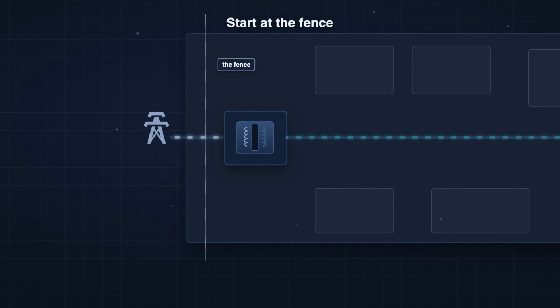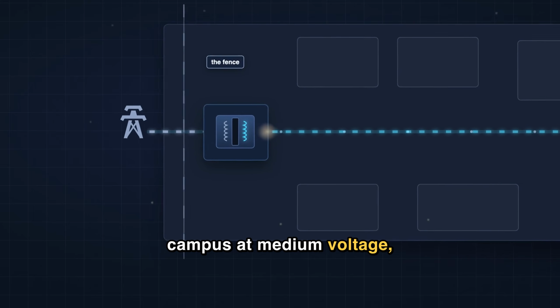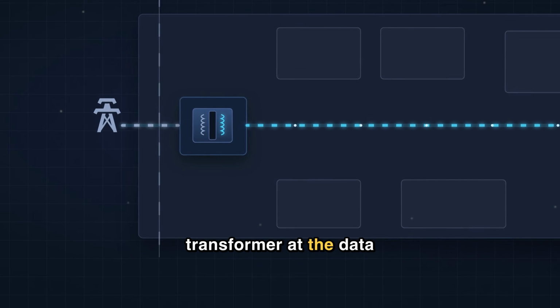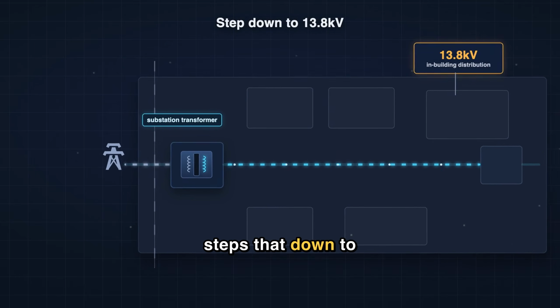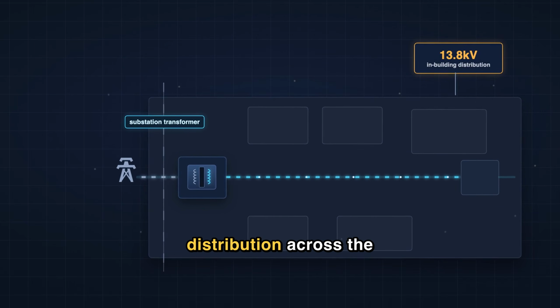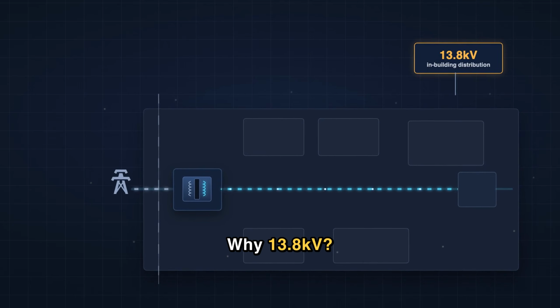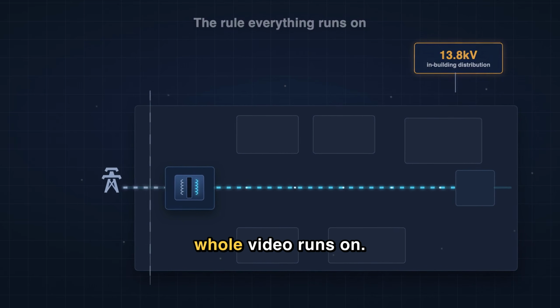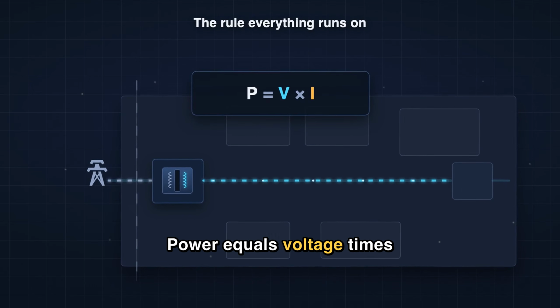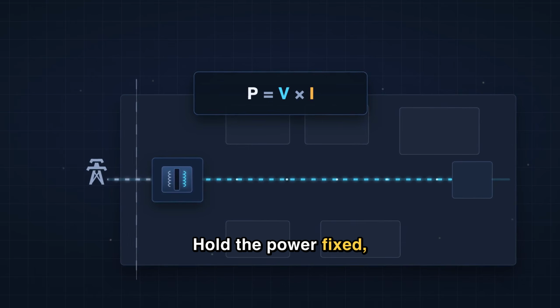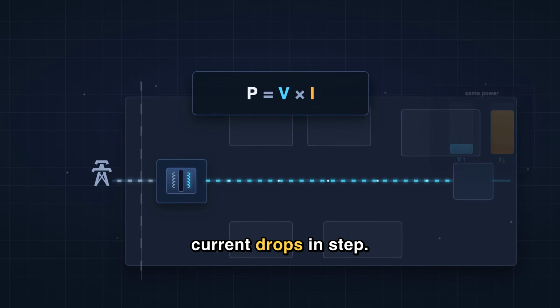Start at the fence. The utility feeds the campus at medium voltage, and the first big transformer at the data center's own substation steps that down to 13,800 volts for distribution across the building. Why 13.8 kilovolts? Here's the rule the whole video runs on. Power equals voltage times current. Hold the power fixed, and if you push the voltage up, the current drops in step.